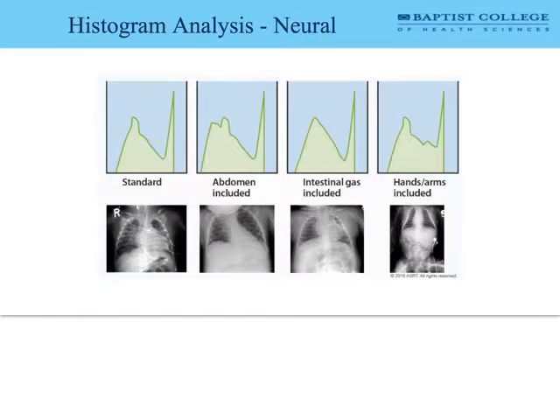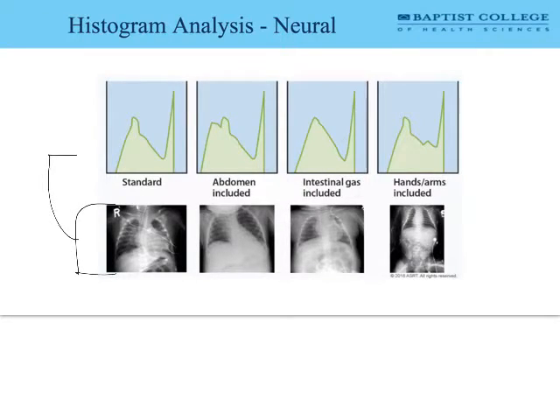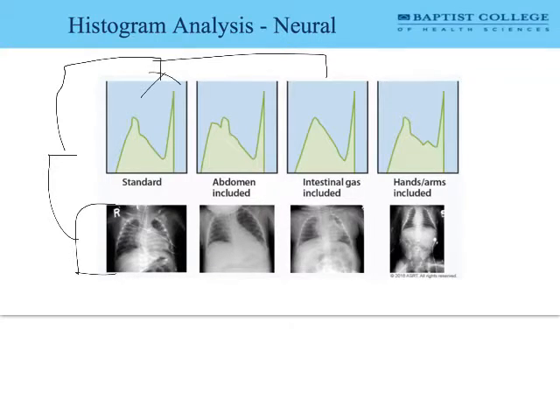Neural histogram analysis is more complex. The data extracted from the plate is compared to two or more predefined histograms, and the image is created after matching image data to one of those predefined histograms. This involves some artificial intelligence, which is why it's called neural histogram analysis. When an image is fed in, the computer searches it against stored references and selects the best match. The computer stores appropriate histograms for each body part, compares minimum and maximum values in the image, and the process of matching captured image values to standardized values is called automatic rescaling.